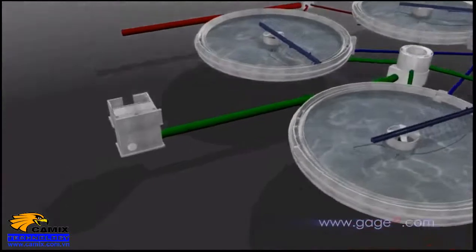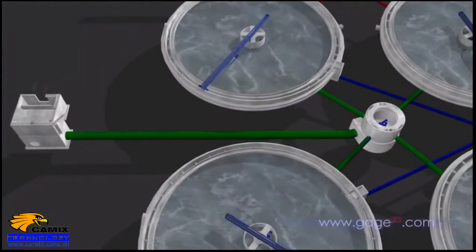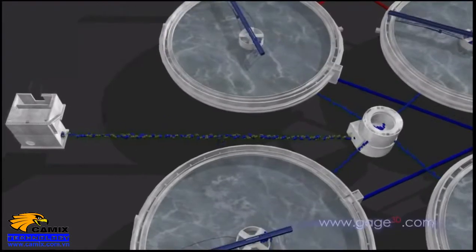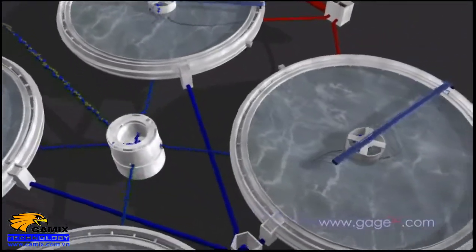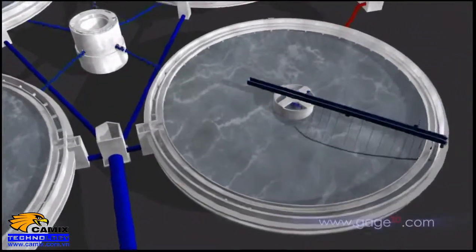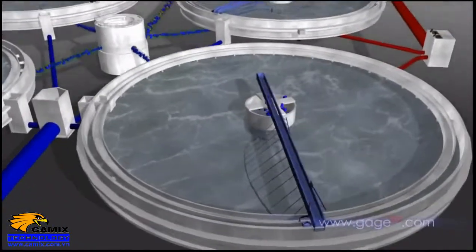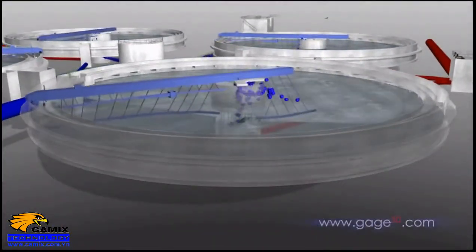Primary clarification is the next step in the treatment process. Wastewater comes up through the center of the clarifier. Water typically sits in the clarifier for one to two hours and becomes quite still. 90-95% of settleable solids fall to the bottom over time and are removed.